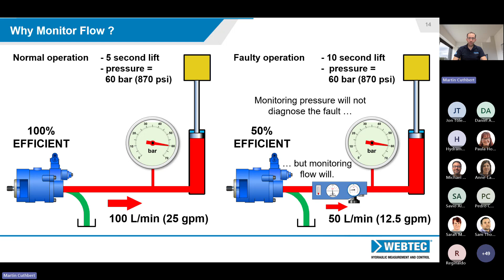So if we want to fault find that particular problem, there's a few ways we can do that. We need to know what the benchmark is of what the ideal flow is. So if we're lucky enough to measure it by time, then we could tell. But in many cases, we don't know that. And so the only real way to do that is with a flow meter in place. So if we put the flow meter after the pump, we can measure what the actual flow rate is. If we look at the spec of the pump, we can see what the flow rate should be coming from it.